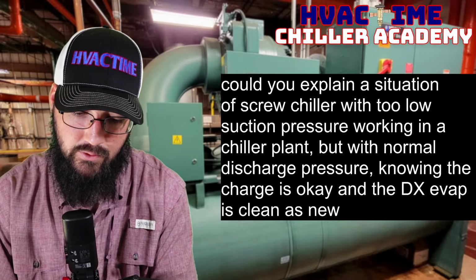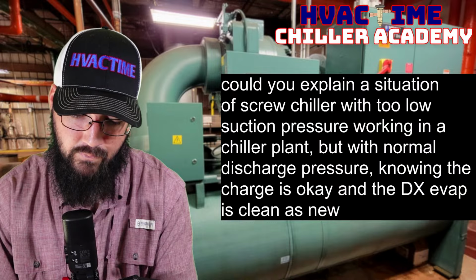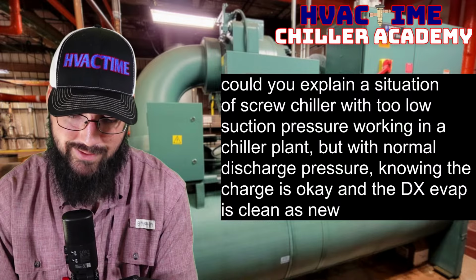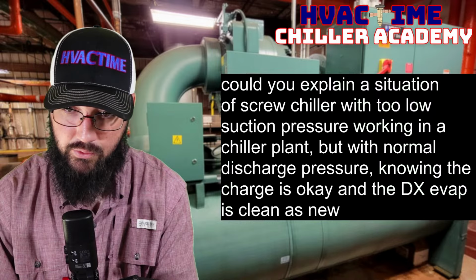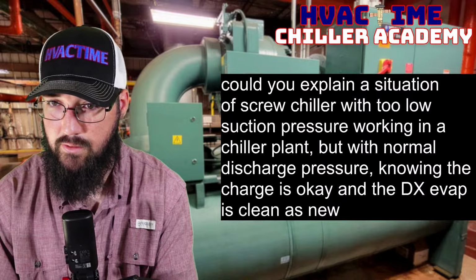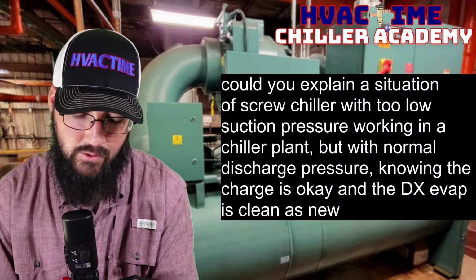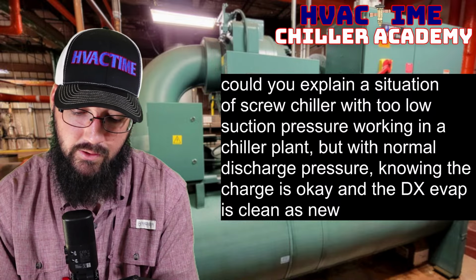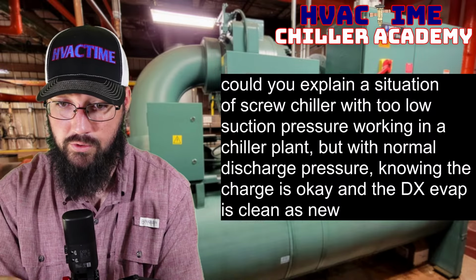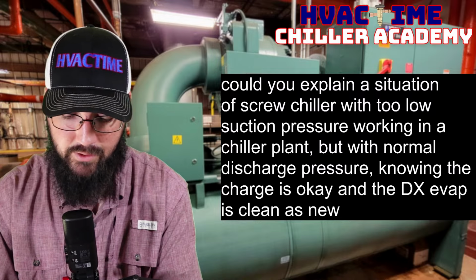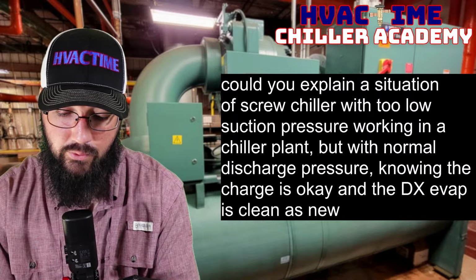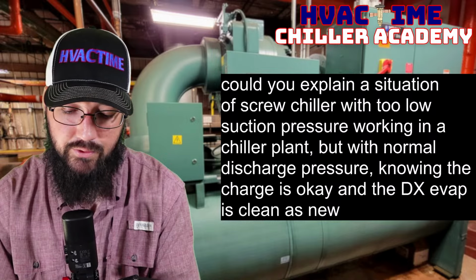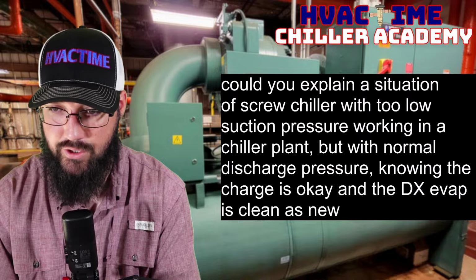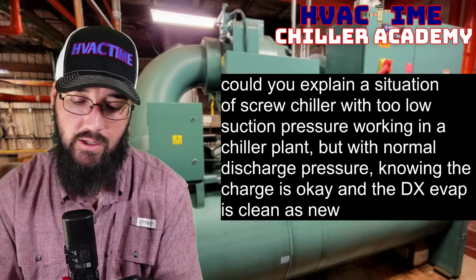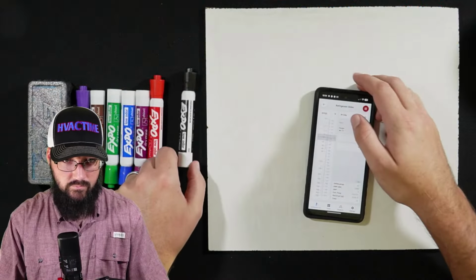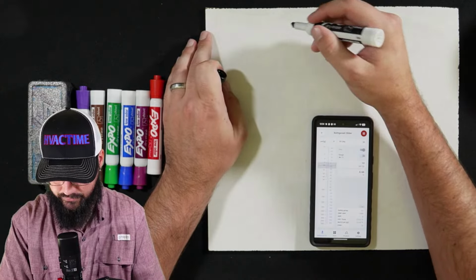So I'm going to pull up my ref tool by Danfoss, and I'm curious. So I'm assuming we're 134A. We don't specify. Yeah, I'm going to assume we're 134. And this is a great troubleshooting conversation. So if we want to just start feeding us info, the more information we have, the better we can give you. Okay, so reading this, if you've got a 20 degree approach and you're at 10 psig on the barrel, assuming it's a 134A machine, that gives us a saturation of, basically, we'll call it 7 degrees.